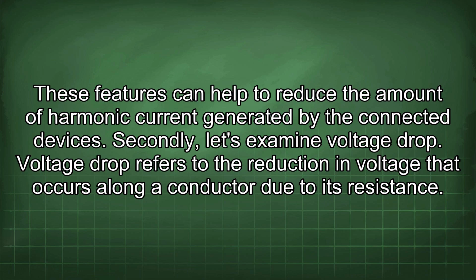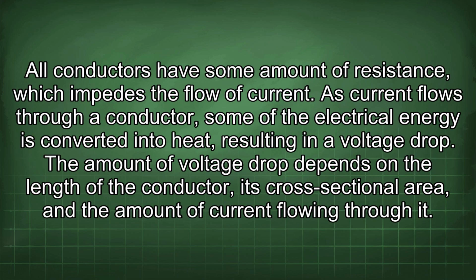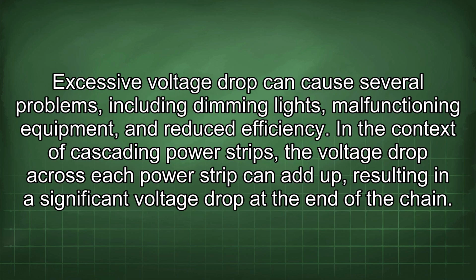Voltage drop refers to the reduction in voltage that occurs along a conductor due to its resistance. All conductors have some amount of resistance, which impedes the flow of current. As current flows through a conductor, some of the electrical energy is converted into heat, resulting in a voltage drop. The amount of voltage drop depends on the length of the conductor, its cross-sectional area, and the amount of current flowing through it. Excessive voltage drop can cause several problems, including dimming lights, malfunctioning equipment, and reduced efficiency. In the context of cascading power strips, the voltage drop across each power strip can add up, resulting in a significant voltage drop at the end of the chain.